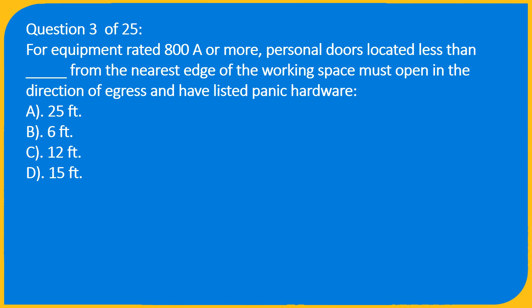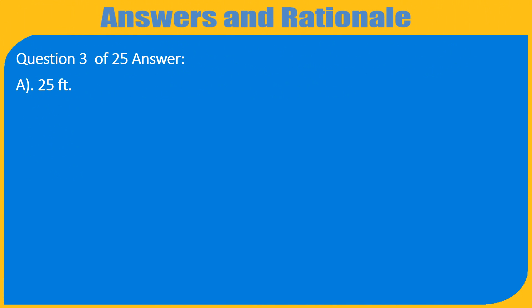Question 3 of 25: For equipment rated 800A or more, personnel doors located less than how many feet from the nearest edge of the working space must open in the direction of egress and have listed panic hardware? A. 25 feet, B. 6 feet, C. 12 feet, D. 15 feet. Answer: A. 25 feet.